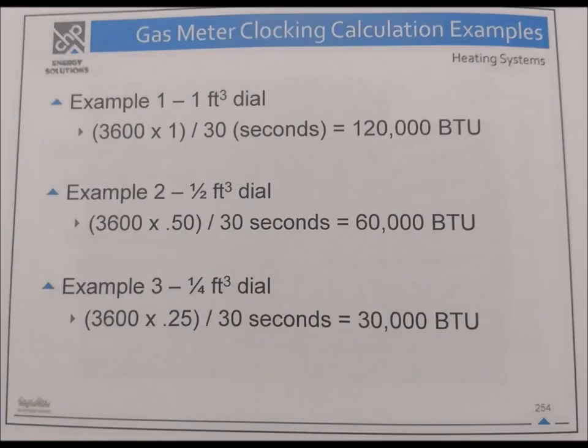Gas meter clocking calculation examples. Example 1: One cubic foot dial — 3,600 times 1 divided by 30 seconds equals 120,000 BTU/hr. Example 2: Half cubic foot dial — 3,600 times 0.50 divided by 30 seconds equals 60,000 BTU/hr. Example 3: One-quarter cubic foot dial — 3,600 times 0.25 divided by 30 seconds equals 30,000 BTU/hr.